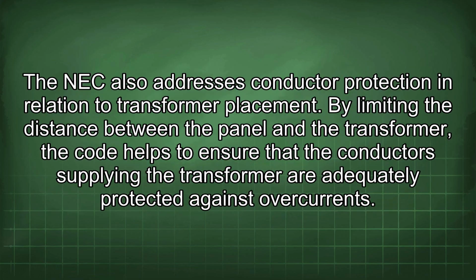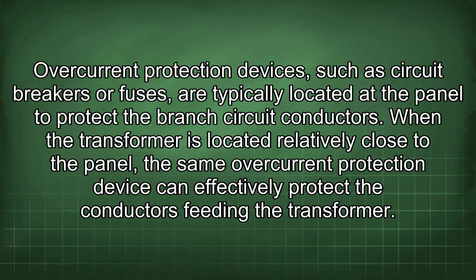The NEC also addresses conductor protection in relation to transformer placement. By limiting the distance between the panel and the transformer, the code helps to ensure that the conductors supplying the transformer are adequately protected against overcurrents. Overcurrent protection devices, such as circuit breakers or fuses, are typically located at the panel to protect the branch circuit conductors.